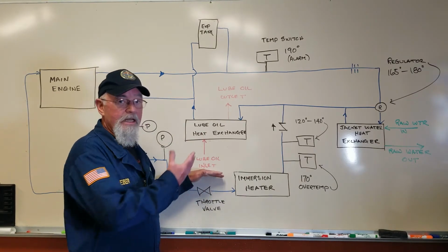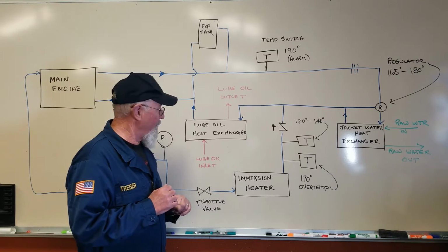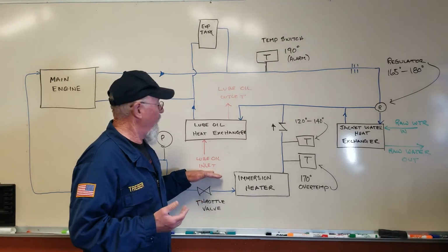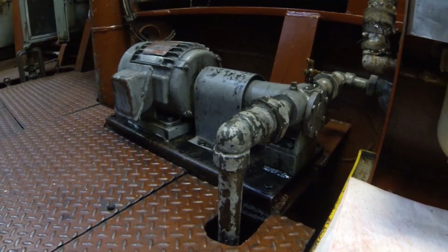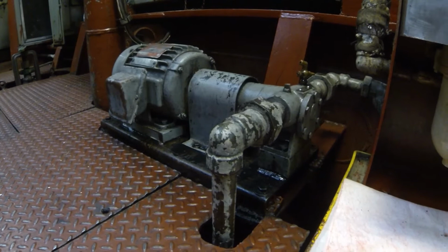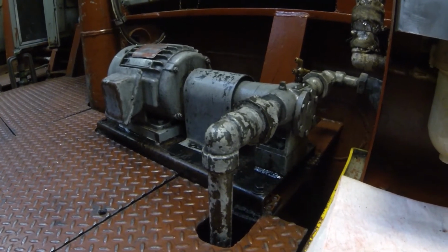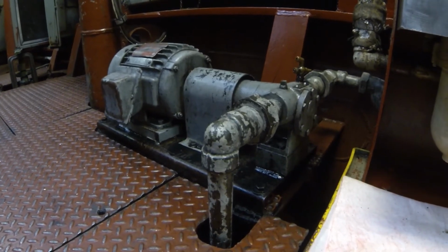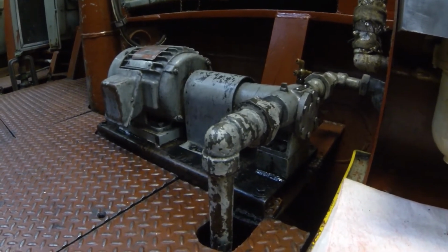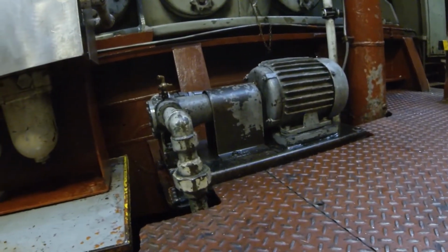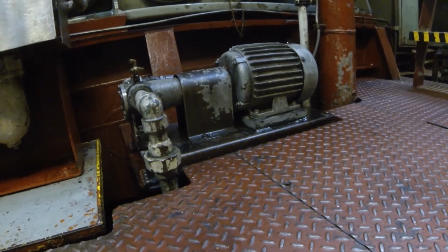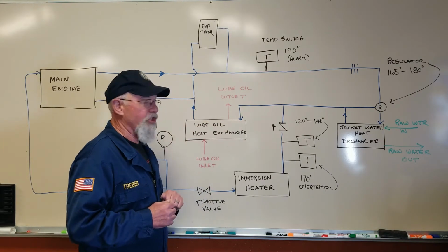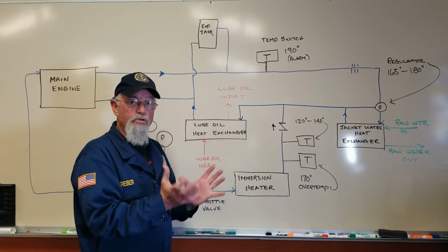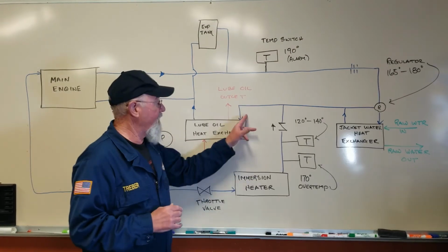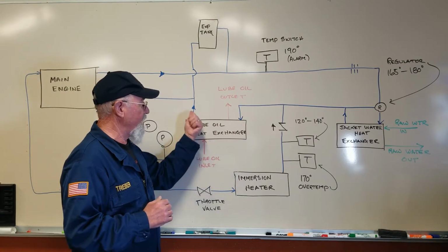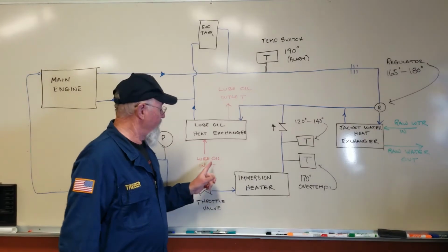At the same time, and I didn't illustrate that, there's a positive displacement rotary gear pump that's taking a suction from the lube oil sump and pumping it through the heat exchanger. This is your positive displacement rotary gear circulating oil pump. One for each engine. So this is a tube and shell heat exchanger, which means there's a bundle of tubes enclosed in a shell. On the outside of the tubes, we've got warm jacket water circulating from one end to the other, and on the inside of the tubes, we've got lube oil circulating.